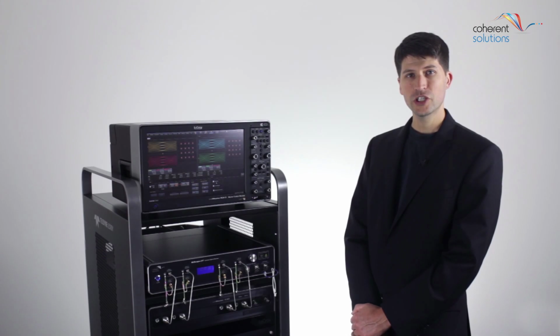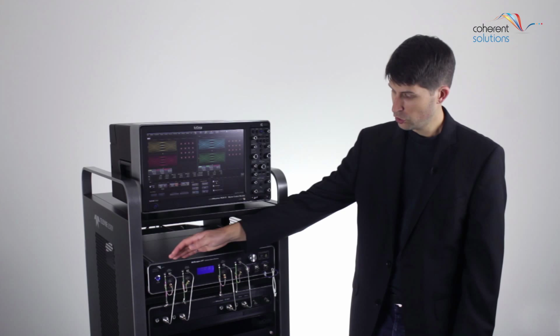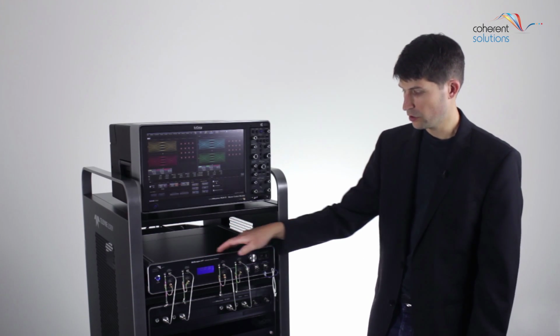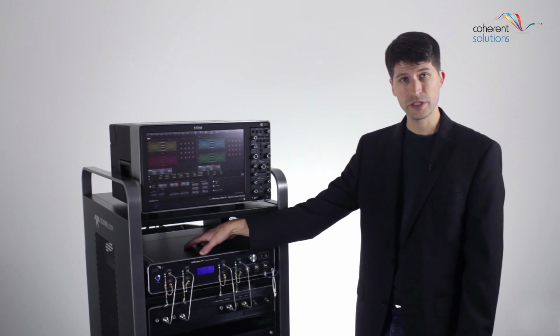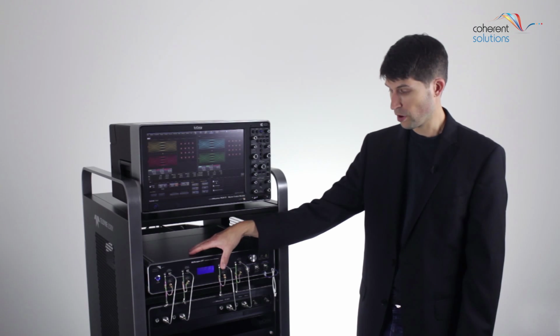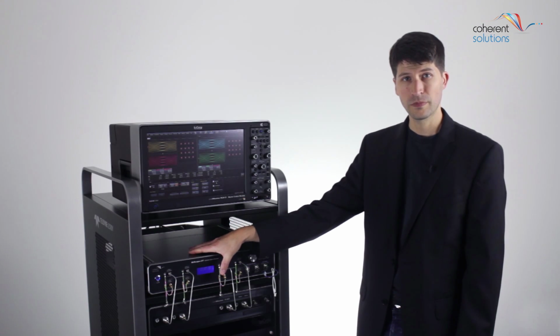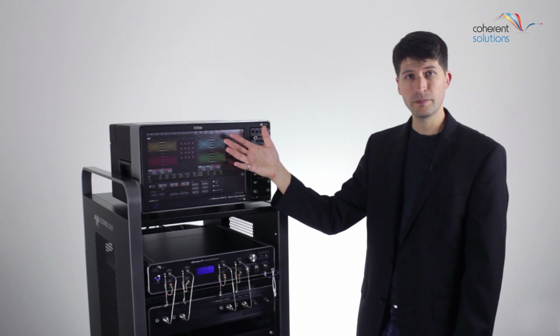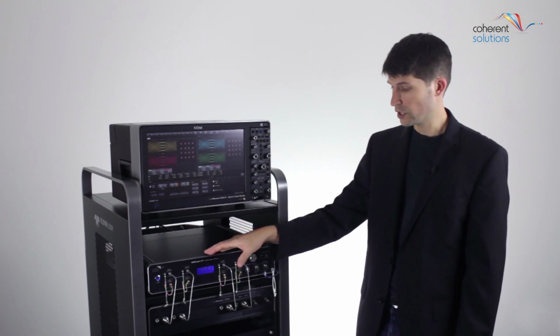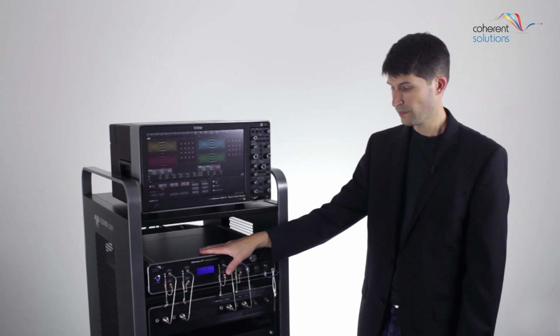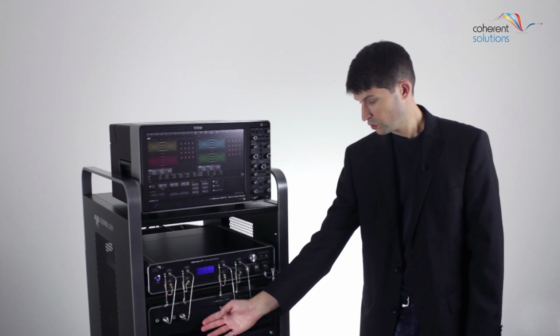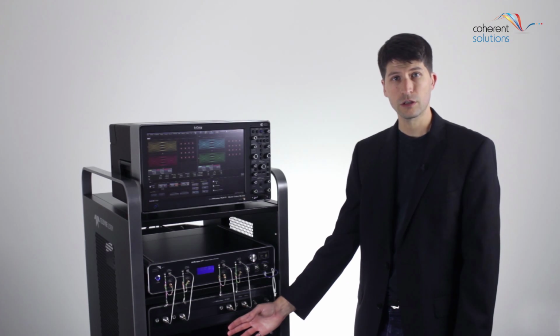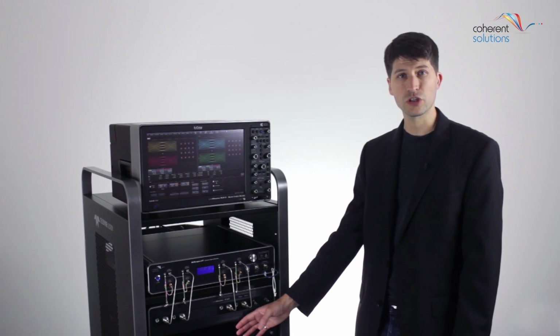Having the Optical Modulation Analyzer configured in this fashion gives you a lot of flexibility. For example, you could replace this golden coherent receiver with your own receiver and test its performance in your system. You still get to use all the powerful analysis capability in the Optical Link OMA software using your own receiver. Or, in the future, you could upgrade this acquisition unit to a higher bandwidth acquisition unit.